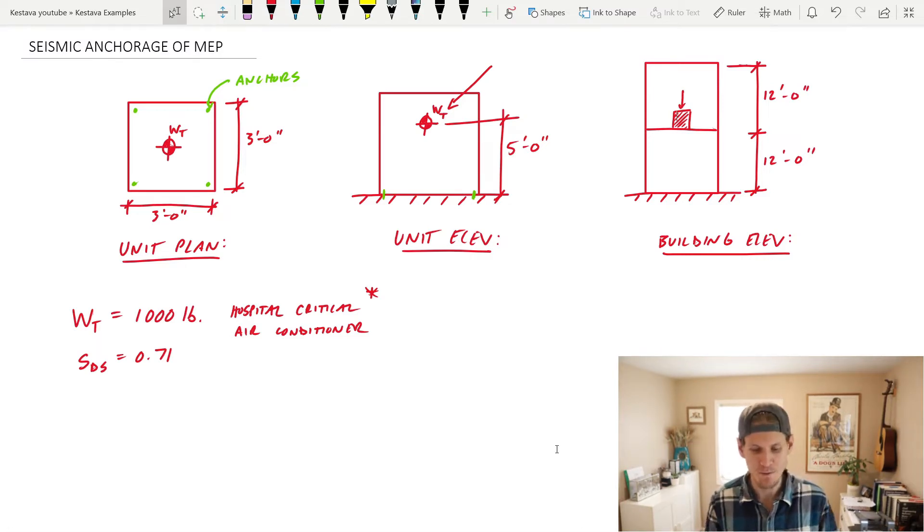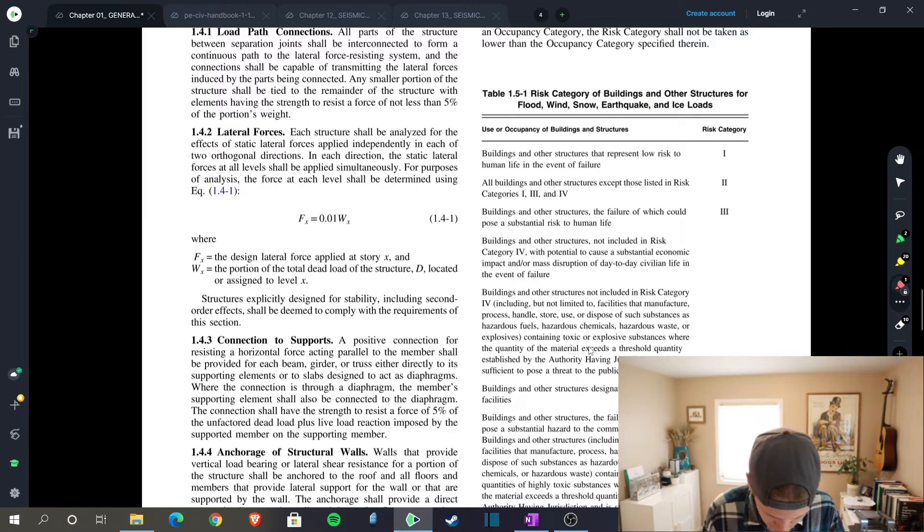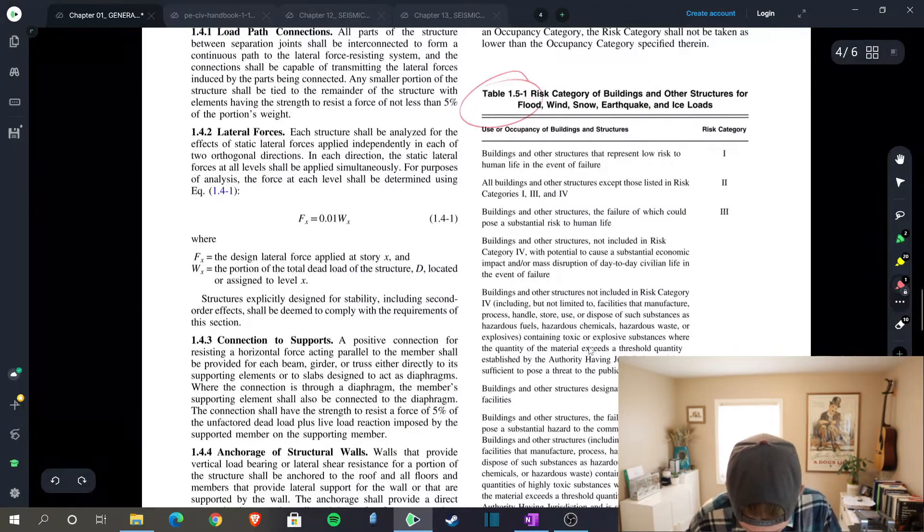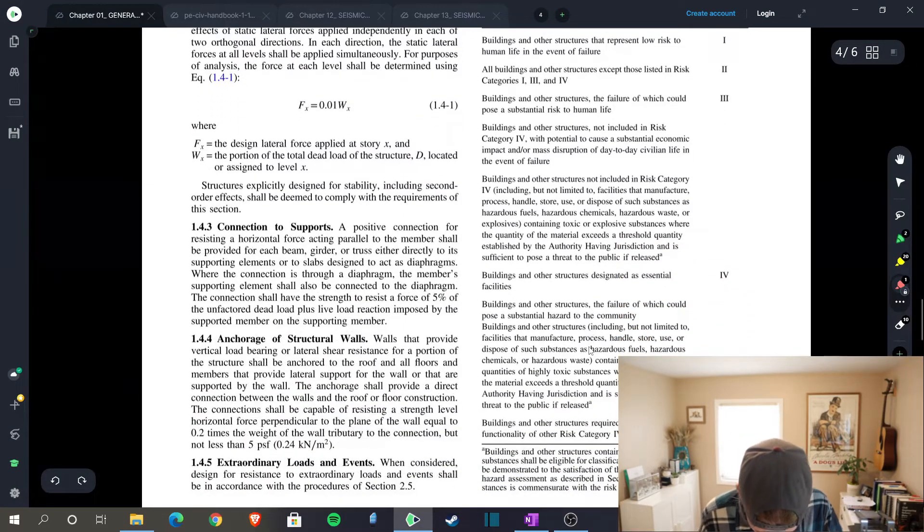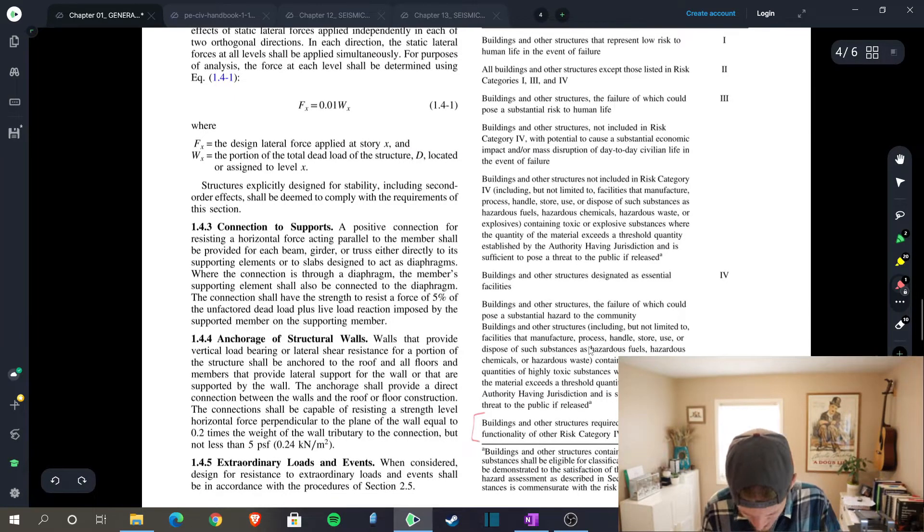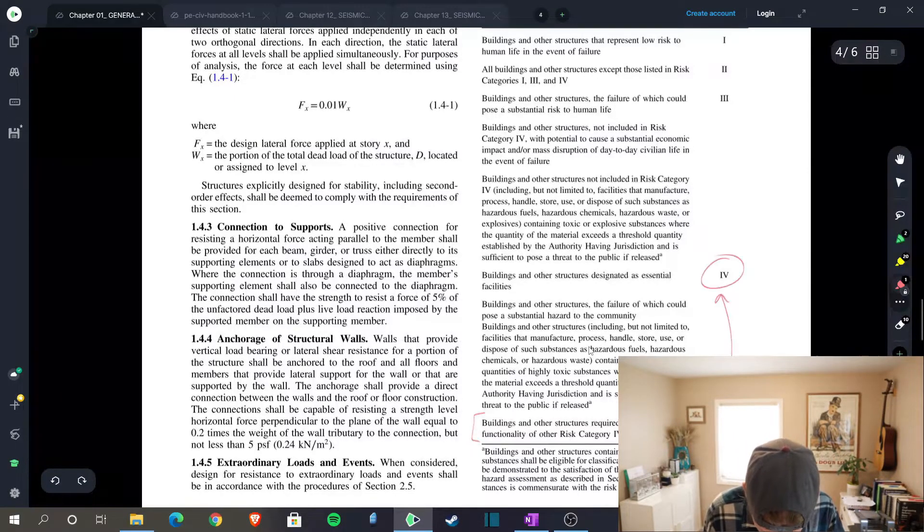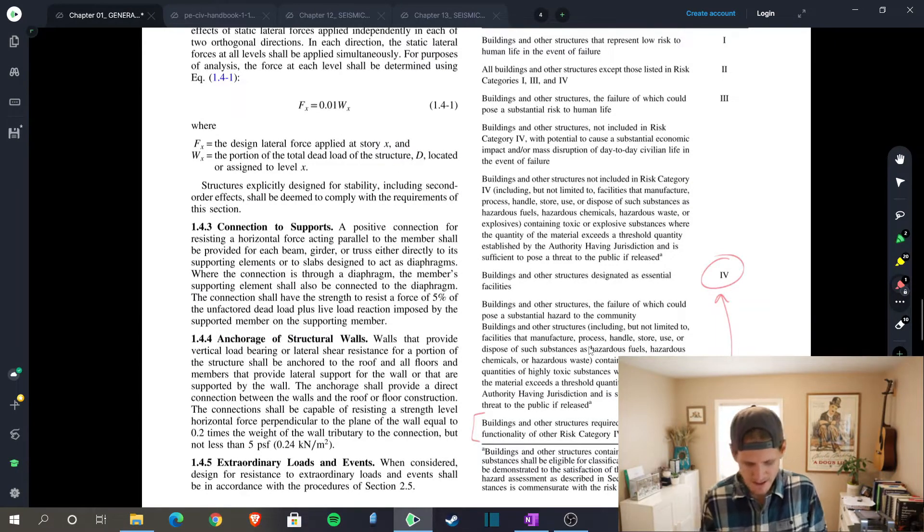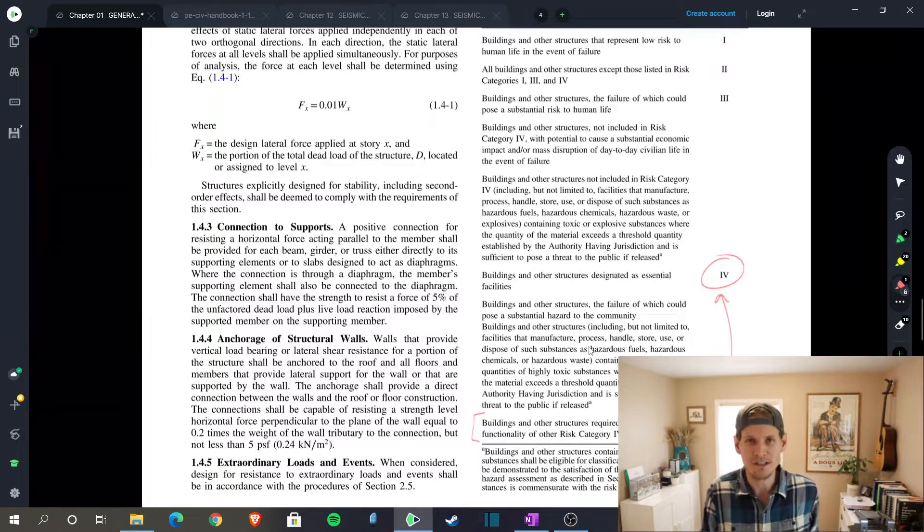So first, let's head to chapter one of the 7-16. Table 1.5-1 is where we find ourselves looking at risk categories based on our component type, and at the bottom, this is the bread and butter that we need from this section, which determines that we are risk category 4.